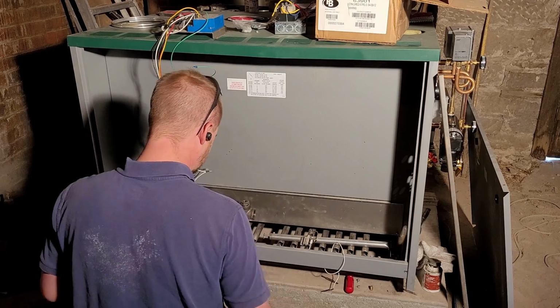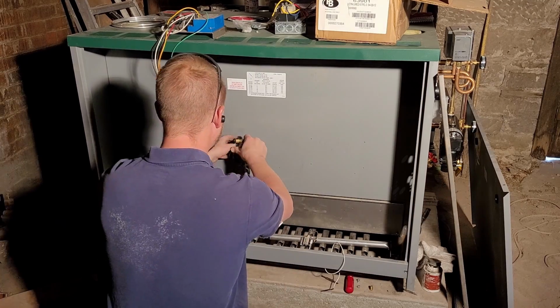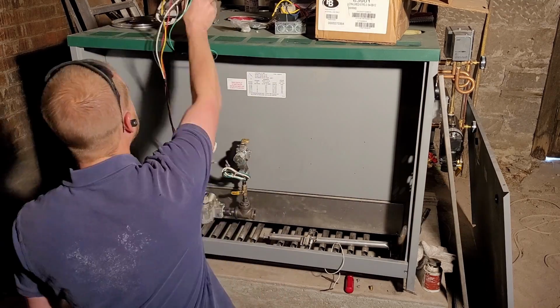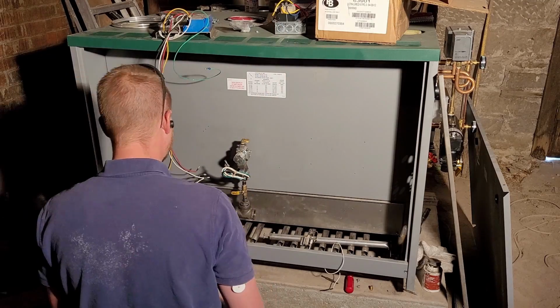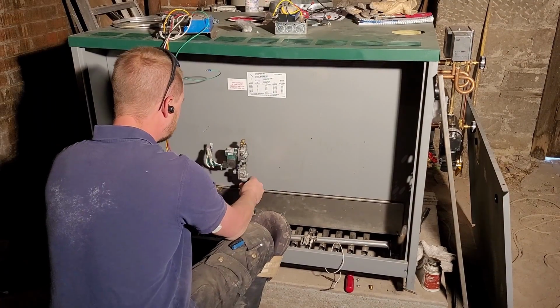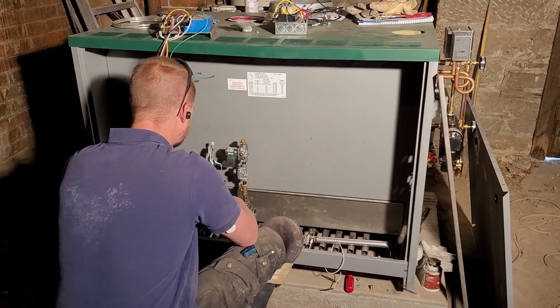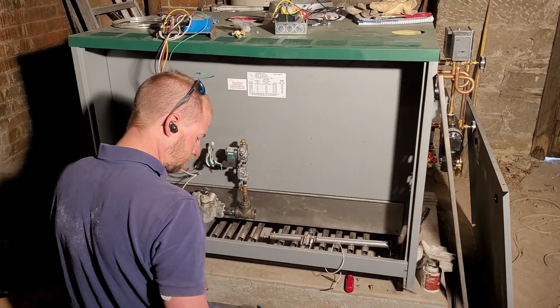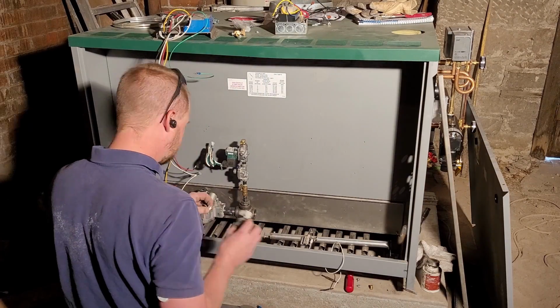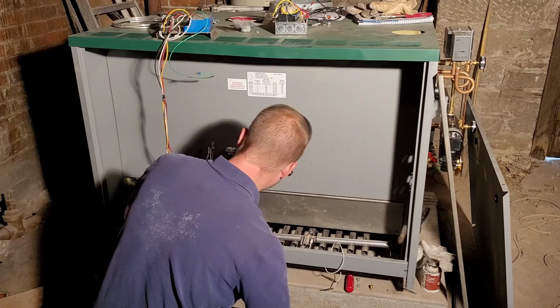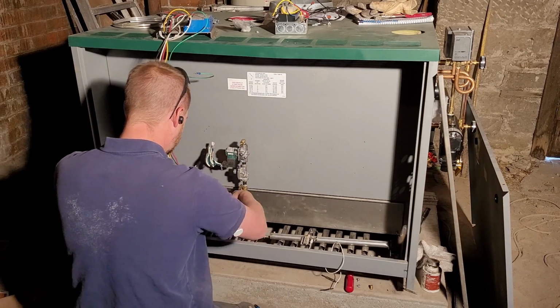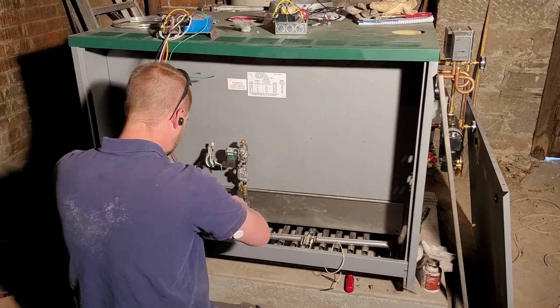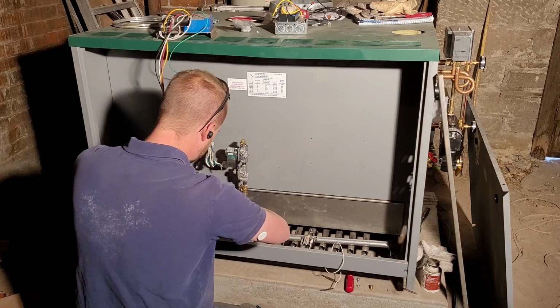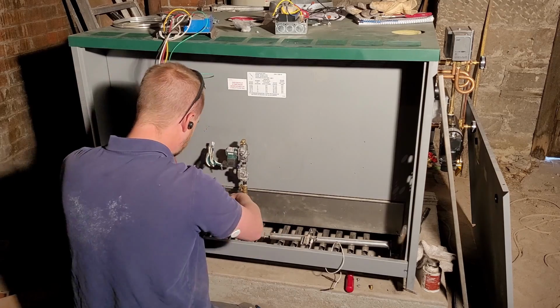So right now I'm installing the pilot. This boiler has its own little pilot operating valve, which is more of a commercial thing. You won't see this on residential boilers. So out of that little solenoid valve, there's quarter-inch aluminum tubing, and that goes down and connects to the pilot. That's what conveys gas to the pilot flame.